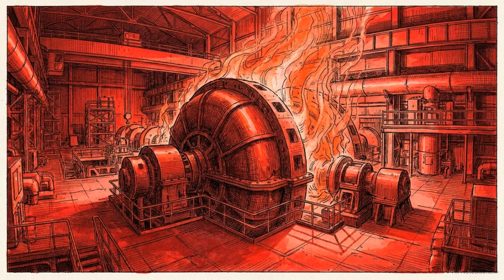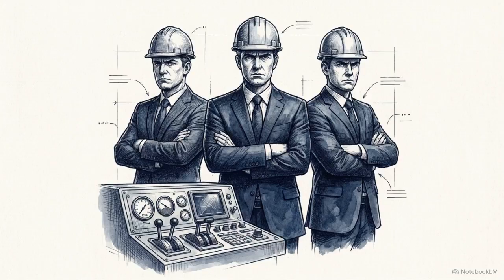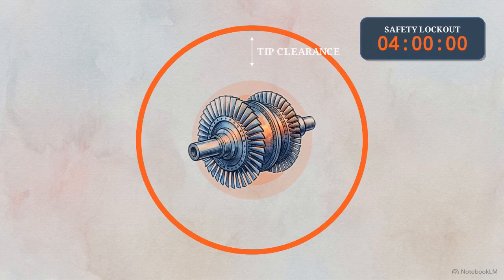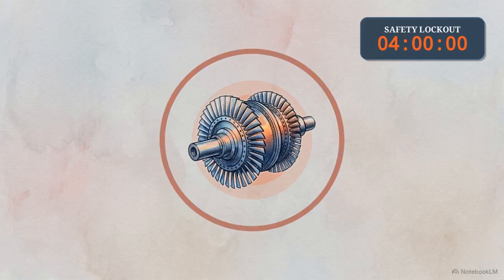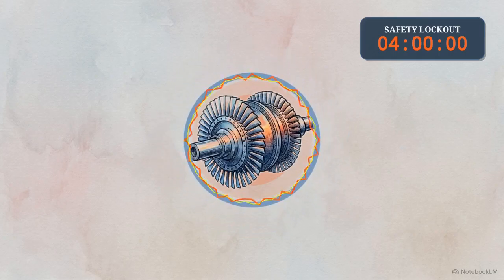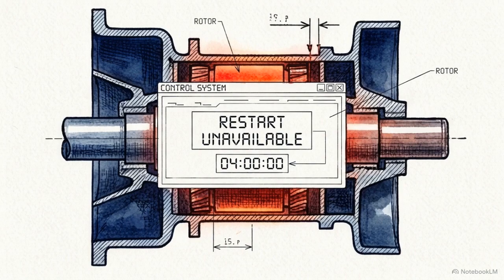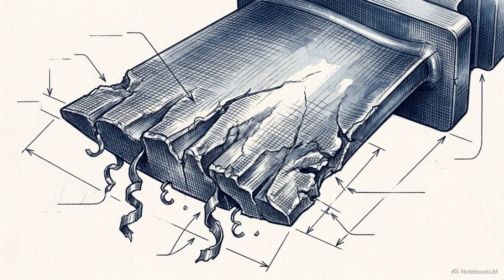But when a high-power turbine trips offline, the focus immediately shifts to the sudden, catastrophic mechanical events taking place inside the engine casing. When a turbine drops offline unexpectedly, the pressure mounts instantly. Plant management demands an immediate restart to restore the lost grid capacity and avoid financial penalties. But forcing a restart on an LM2500 without accounting for the differential cooling rates between the hot inner rotor and the rapidly shrinking outer casing risks grinding the blades directly into the metal. Understanding this strict 4-hour lockout rule and the thermodynamics of hot rotor rub is the only way to prevent the single most expensive mistake a field engineer can make.